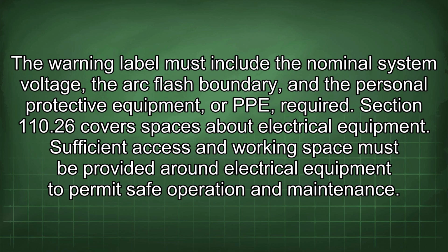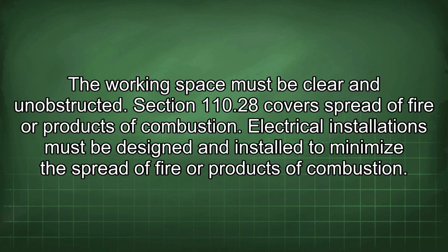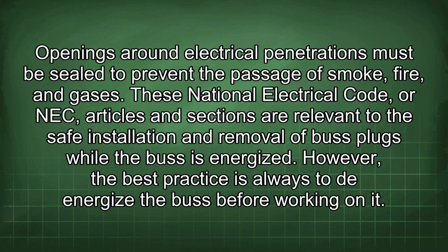Section 110.26 covers spaces about electrical equipment. Sufficient access and working space must be provided around electrical equipment to permit safe operation and maintenance. The working space must be clear and unobstructed. Section 110.28 covers spread of fire or products of combustion. Electrical installations must be designed and installed to minimize the spread of fire or products of combustion. Openings around electrical penetrations must be sealed to prevent the passage of smoke, fire, and gases.